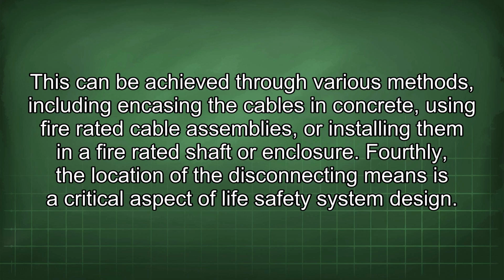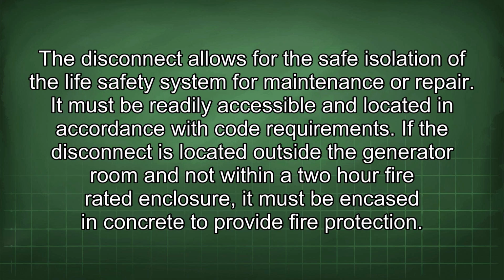Fourthly, the location of the disconnecting means is a critical aspect of life safety system design. The disconnect allows for the safe isolation of the life safety system for maintenance or repair. It must be readily accessible and located in accordance with code requirements. If the disconnect is located outside the generator room and not within a 2-hour fire-rated enclosure, it must be encased in concrete to provide fire protection.